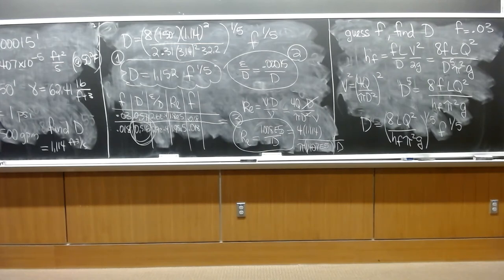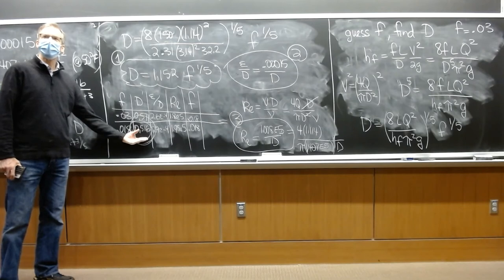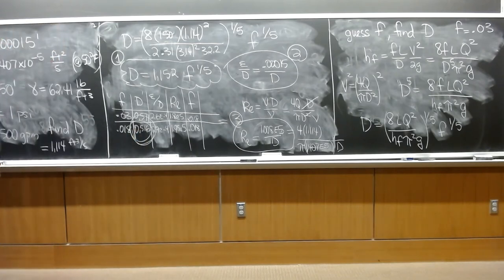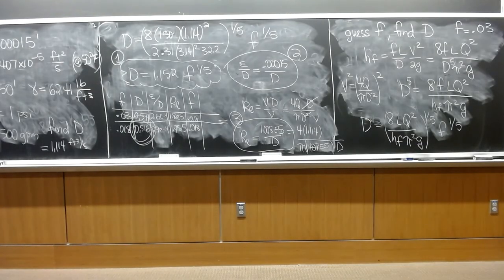You'd have to go up to the next commercially available size, which is probably an 8-inch. I'm not sure if that's the way they wrote it in the solution, but there isn't a limitless supply of commercially available pipes. You'd say, well, I need something at least 0.516 feet in diameter, which I believe is going to be an 8-inch pipe. Let's see what they say in the solution.